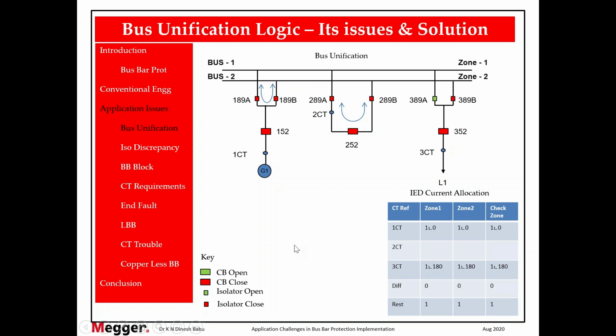Everything eliminated. Second concept: read all the CTs in all the zones, irrespective of isolator status. So we are not worried about isolator status. All zones will read as check zone. Okay. If we are reading like this, then what will happen? For a zone 1 fault, zone 2 also will trip. For a zone 2 fault, zone 1 also will trip. Then there is the issue of how I can differentiate the zones. The answer is we have to trip both zones, because now it is not a 2-bus arrangement. The moment you close these two isolators, we call this a single bus.